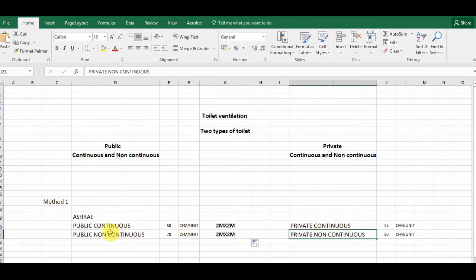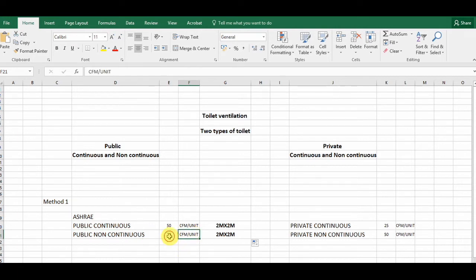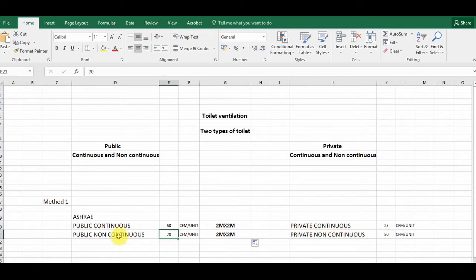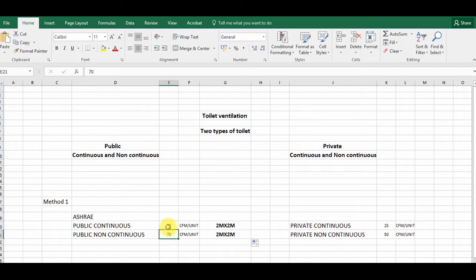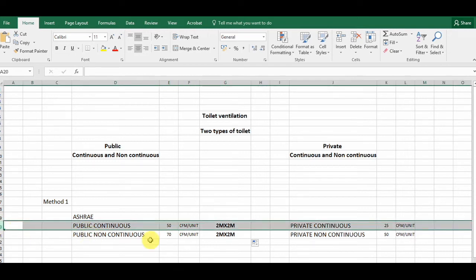For a public non-continuous toilet, we remove 70 CFM per toilet. For private continuous, it is 25 CFM per toilet, and for private non-continuous it is 50 CFM per toilet. The non-continuous values are higher because when the exhaust fan is switched off, smell accumulates more, so we need to remove more air when it runs. In continuous mode, the fan runs constantly through ducting, so lower values suffice.